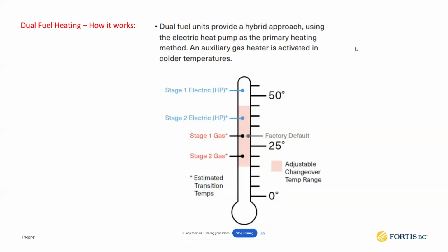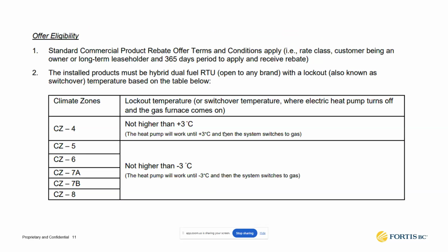Well, as you can see here graphically in this thermometer, the electric heat pump will be providing your heat during mild outdoor conditions, and then the gas will take over at the cold temperature, at freezing or near freezing. This changeover temperature from electric heat pump to the gas is adjustable in most systems, but we established in our rebate program that the switchover temperature had to be not higher than 3 degrees C for climate zone 4.